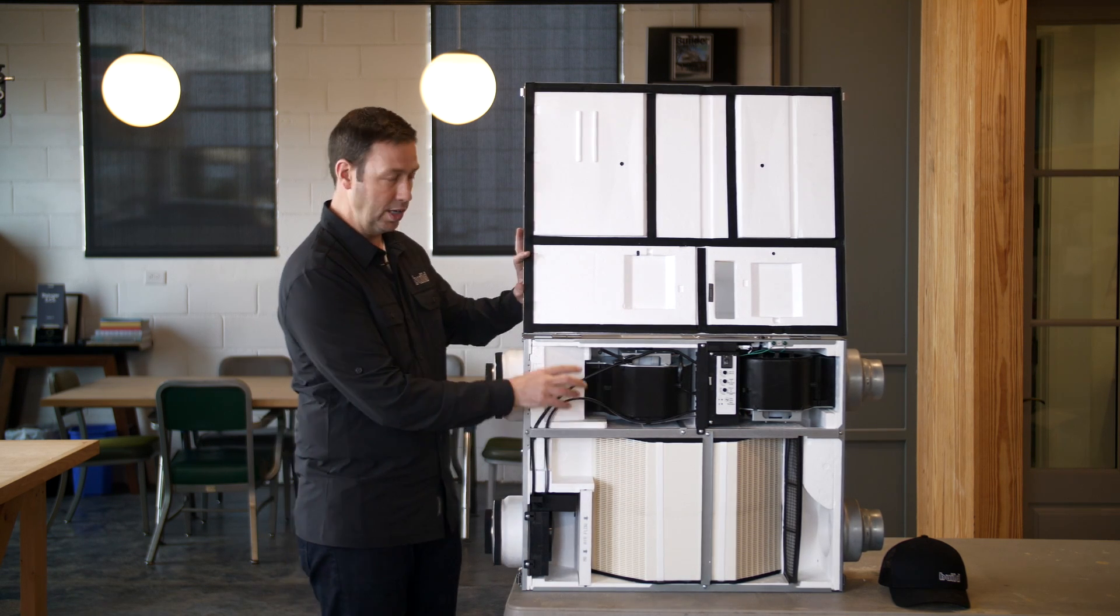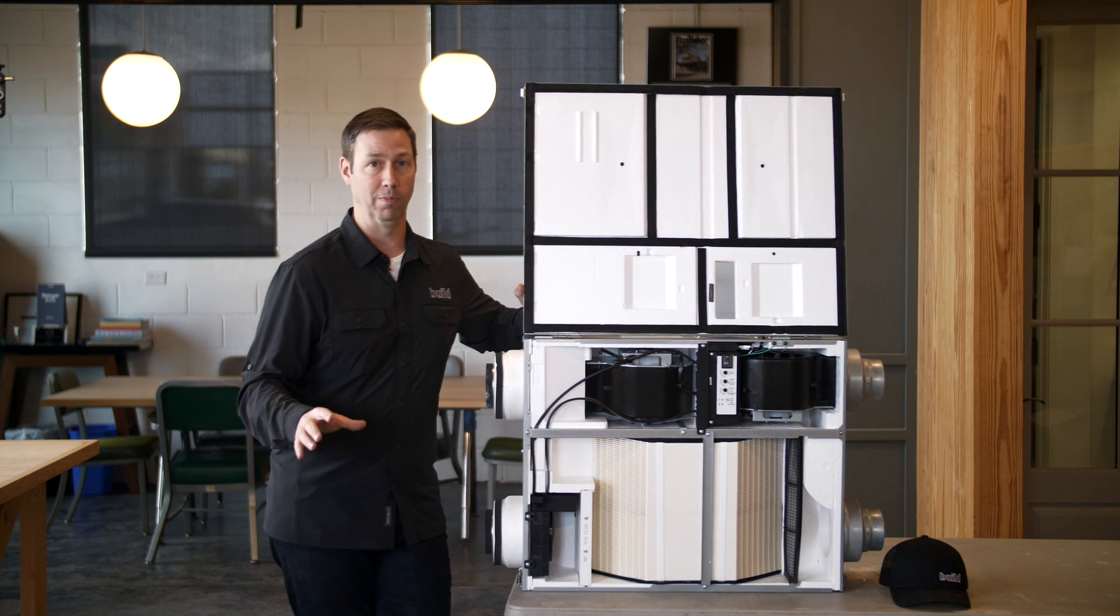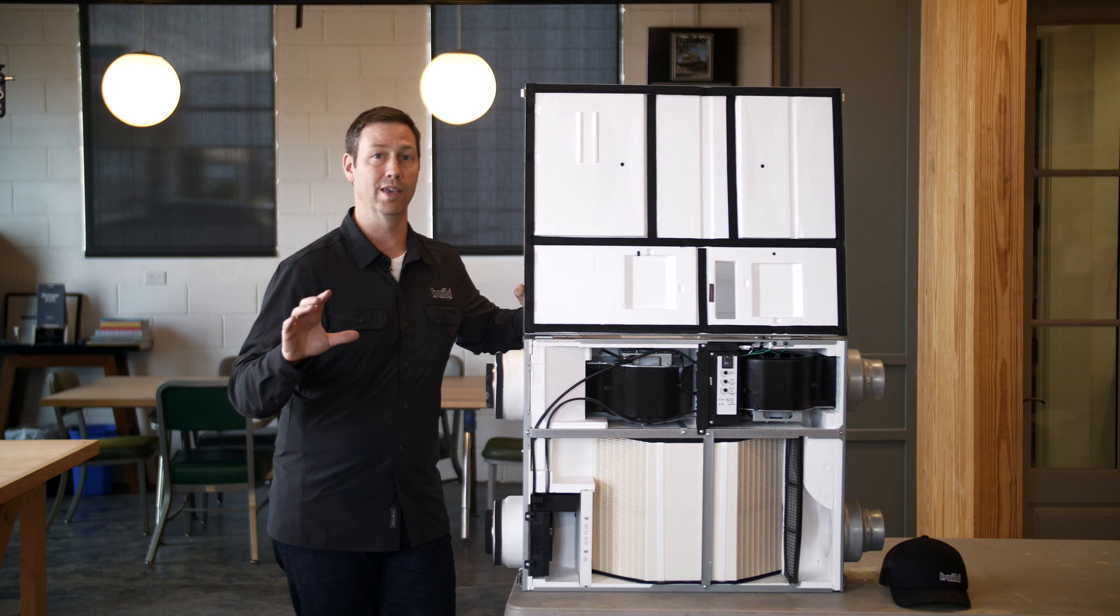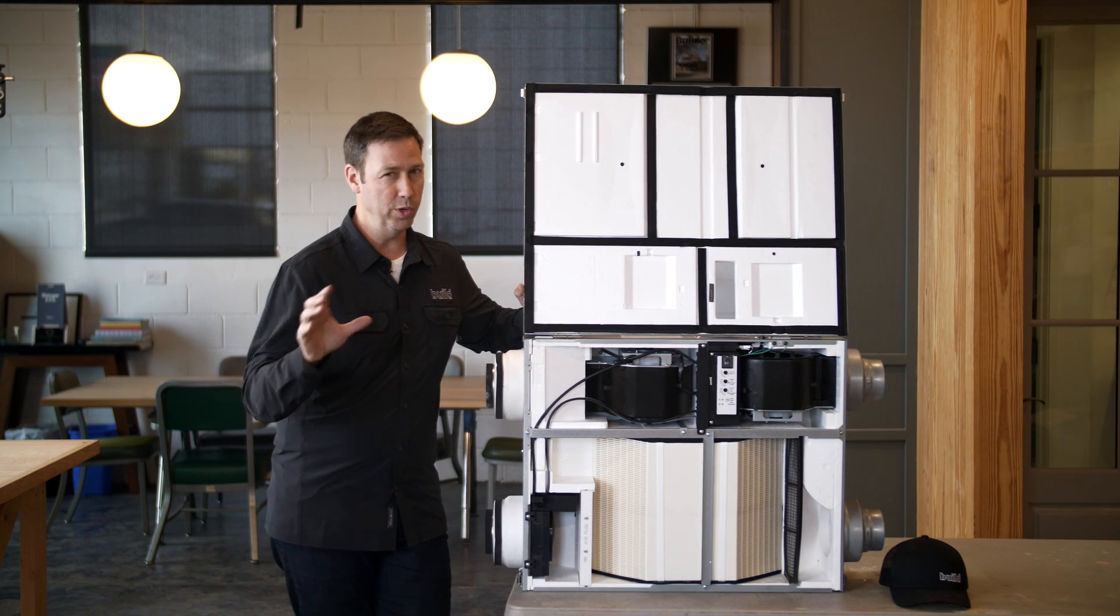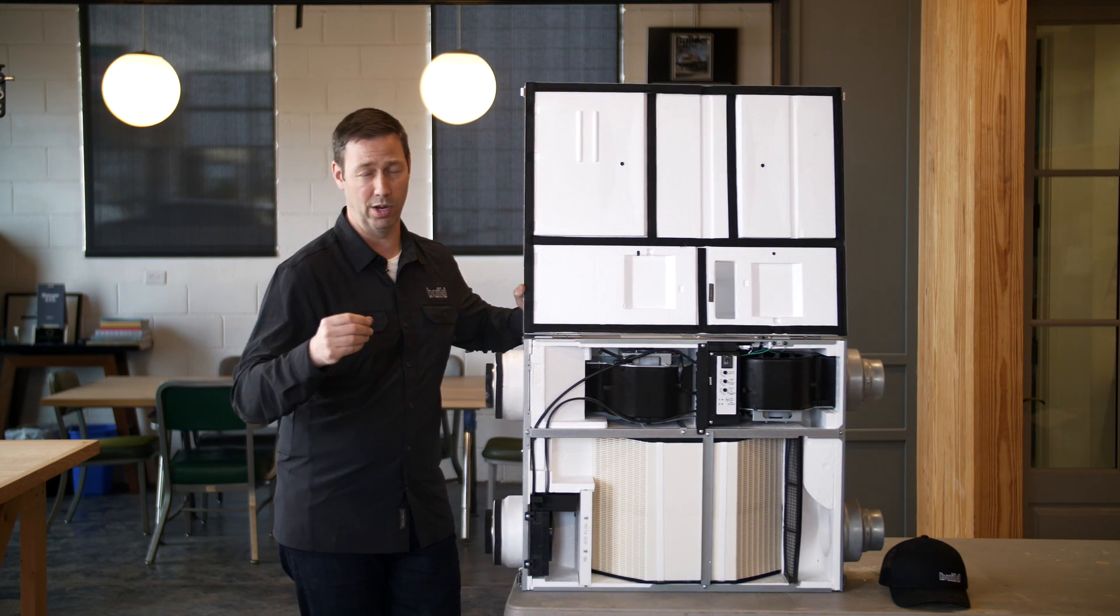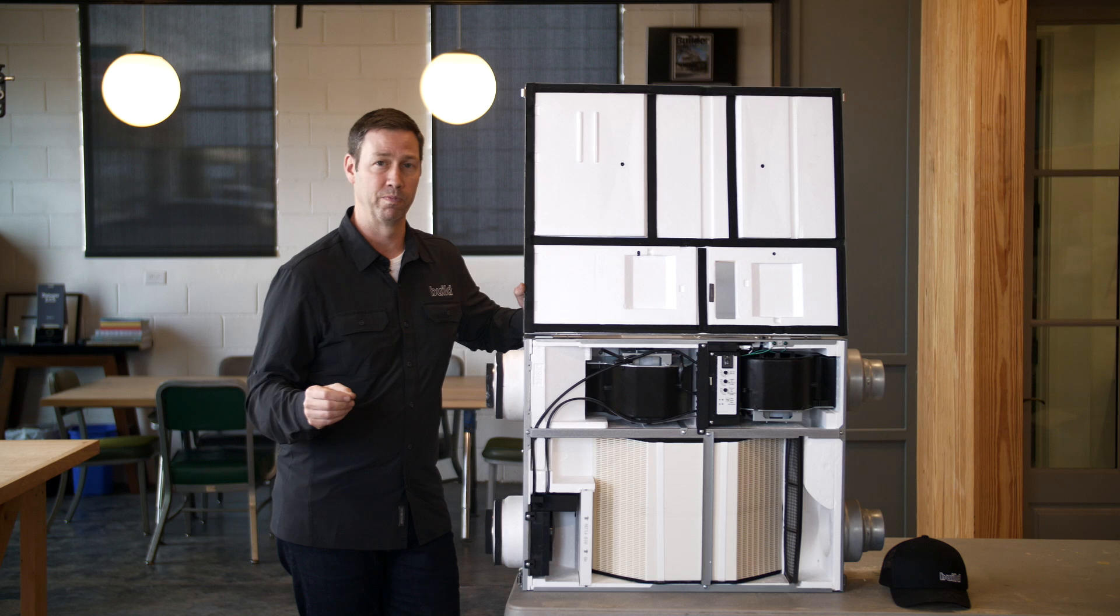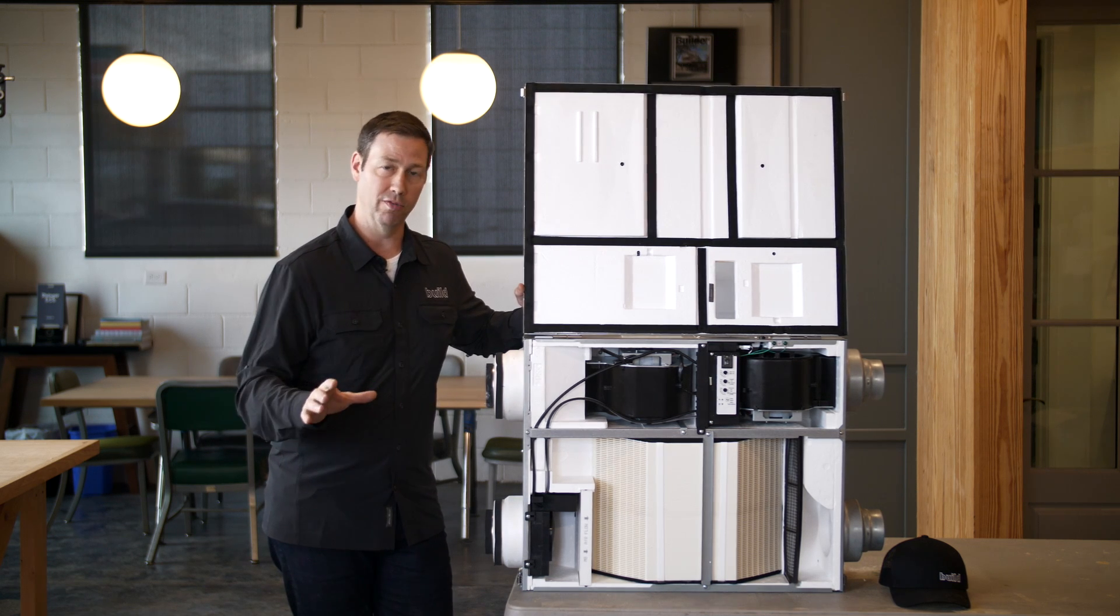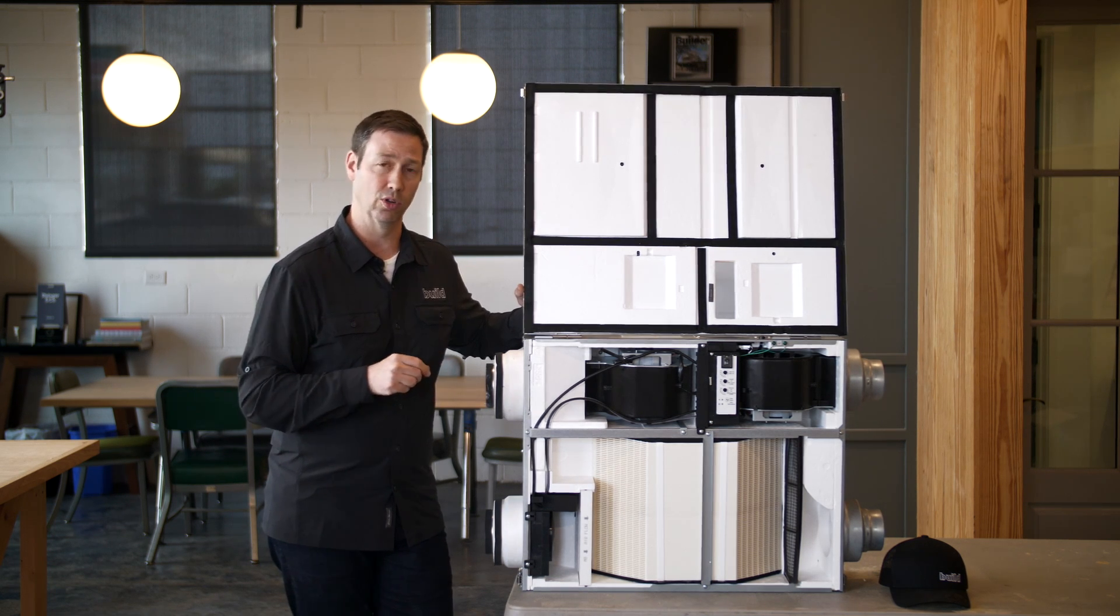Now the beauty of an ERV is it also acts as an HRV. An HRV, on the other hand, does not move moisture. It's only a heat recovery. So which one do we choose? If we're in the north and we're in a really cold climate and it's not particularly humid most of the time, an HRV is going to work. And typically HRVs are a little less expensive.